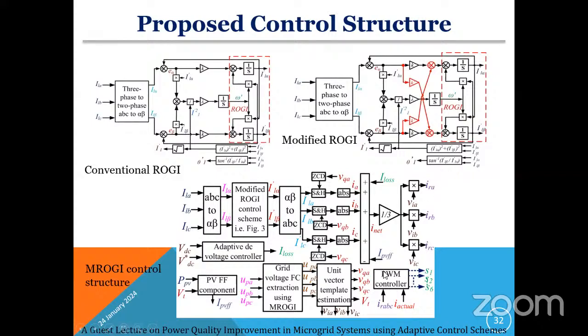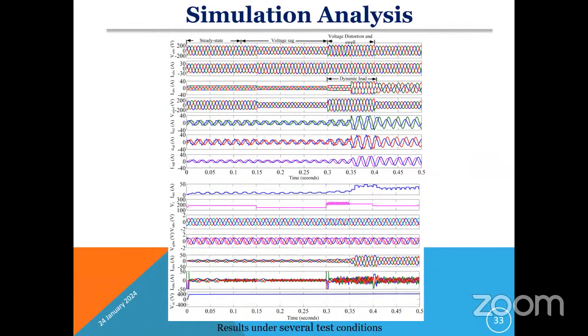Three-phase reference current and actual currents we have given to the PWM controller. By using these two currents, reference current and actual currents, the controller can calculate the switching signals S1 to S6 of the inverter. All these PWM signals we have given to the grid connected inverter for harmonic mitigation in the system. So this is the simulation result.